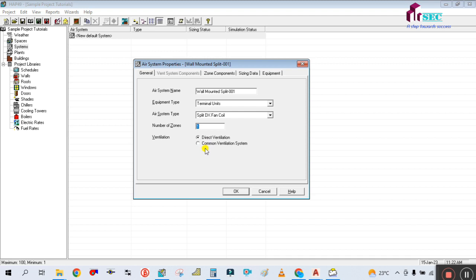The ventilation is set to Direct Ventilation - there is no common ventilation system. If we were using a fresh air FAHU, then Common Ventilation System would be applicable. Here we select Direct Ventilation, meaning we are not using any dedicated ventilation system. Once you select Terminal Unit, the ventilation system component will be disabled - it is not applicable for this type of system. It will only be active for system types other than Terminal Unit.